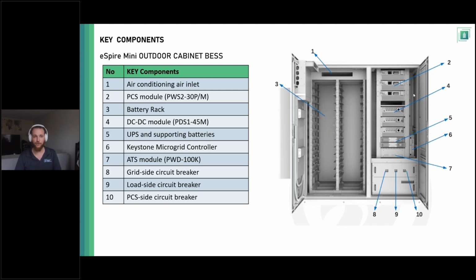The number 2 shows 30 kW bidirectional inverter segments that we can do 30, 60, or 90 kW of output power. So like I mentioned, the 30 kW output unit can output natively at 3-phase 208. You don't need an external transformer to step down or an isolation transformer to go from delta to Y. The 30 kW unit, just one inverter, can handle 3-phase 208.